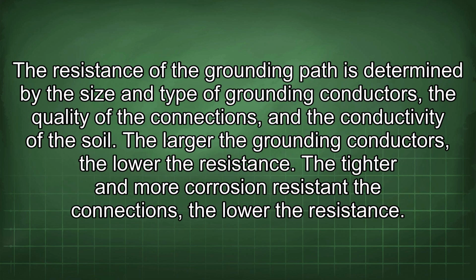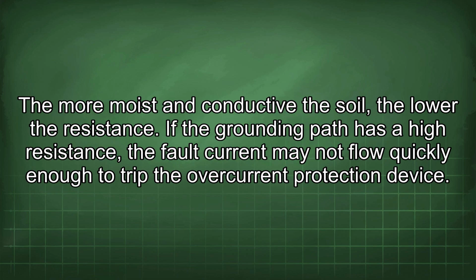The resistance of the grounding path is determined by the size and type of grounding conductors, the quality of the connections, and the conductivity of the soil. The larger the grounding conductors, the lower the resistance. The tighter and more corrosion-resistant the connections, the lower the resistance. The more moist and conductive the soil, the lower the resistance.